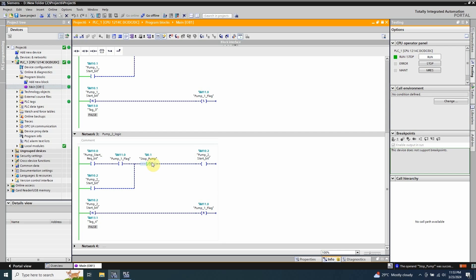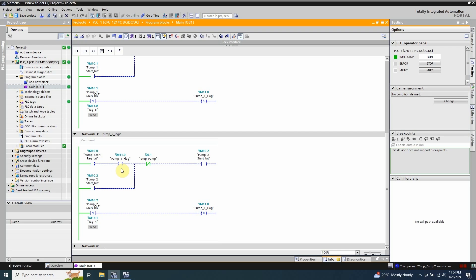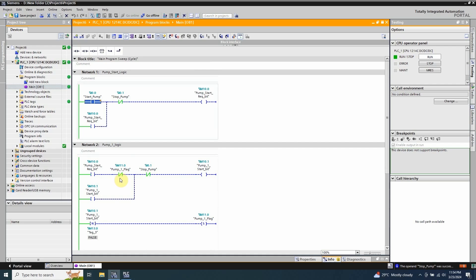Now if we press the stop pump button I0.1, this will turn off the pump 2 start bit M10.2 and turns off pump number 2. As soon as the pump 2 start bit M10.2 turns off, on the negative edge it will reset the pump 1 flag bit M11.0. This will open the normal open contact and prevent pump 2 from starting on the next pump start request. If we come back to network 2, this normal close contact bit M11.0 is again closed, and it will allow pump 1 to start on the next pump start request.